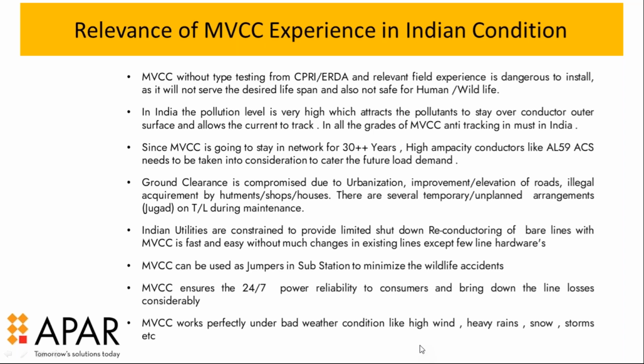And MVCC is very useful especially on the 33 kV and 66 kV networks in Indian utilities for use as jumpers. They face a lot of problems with big kites and eagles, which have a big wingspan. Once they sit on the line and spread their wings to take off, they come in contact and they die. So when we use these covered conductors as jumpers, these fatalities are reduced drastically.